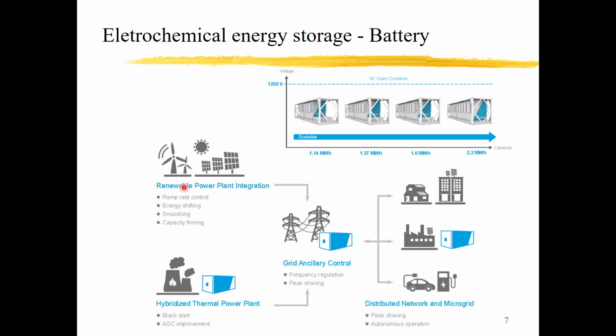For battery systems, if we use the battery as energy storage and work with renewable power plant integration, we can do ramp rate control. That means if we want to increase the output of solar or other renewable energy systems, the power cannot be increased suddenly by a very large amount, because the power system cannot afford a sudden increase of power. So we have to use ramp rate control. Ramp rate control means if you want to increase the power, you have to increase it at a reduced slope, at a reduced rate. On the other hand, when you want to reduce the power output of the renewable energy, you have to reduce it gradually. You cannot reduce it suddenly. That is called ramp rate control.